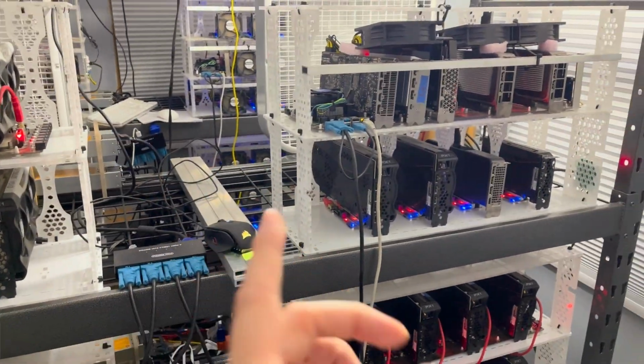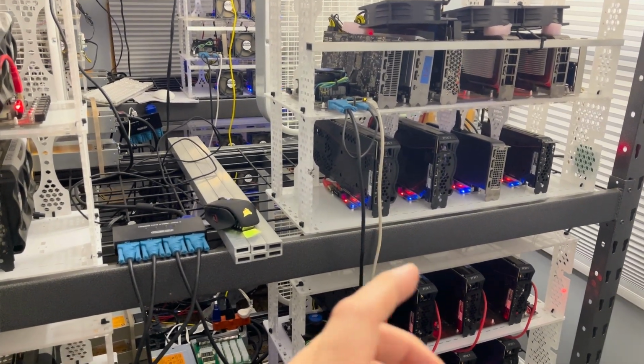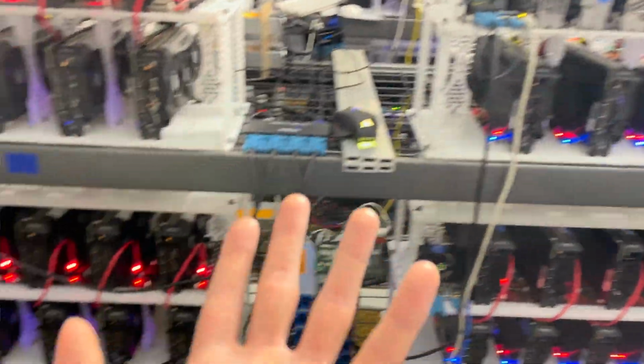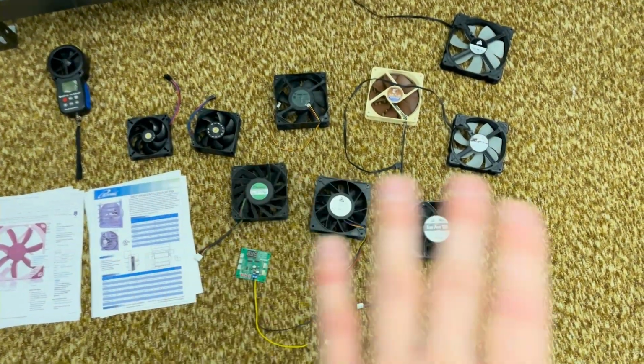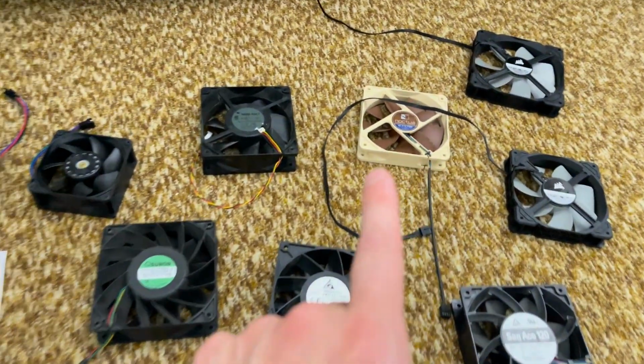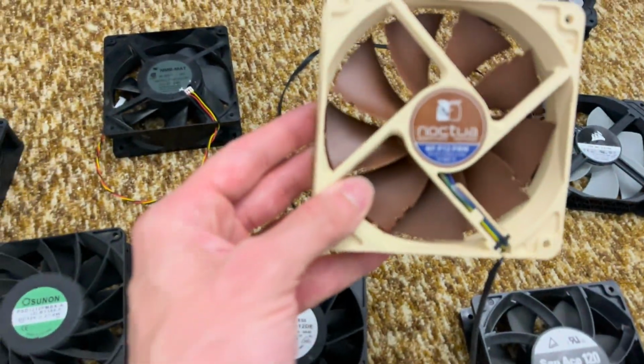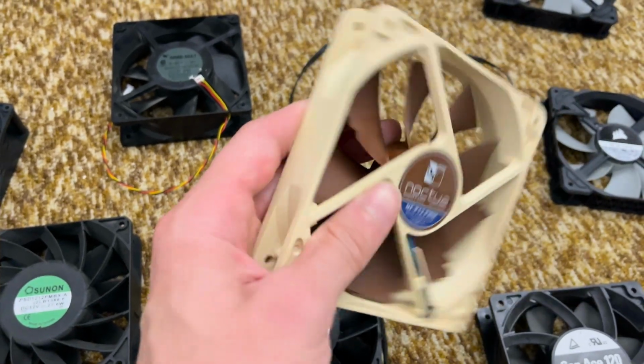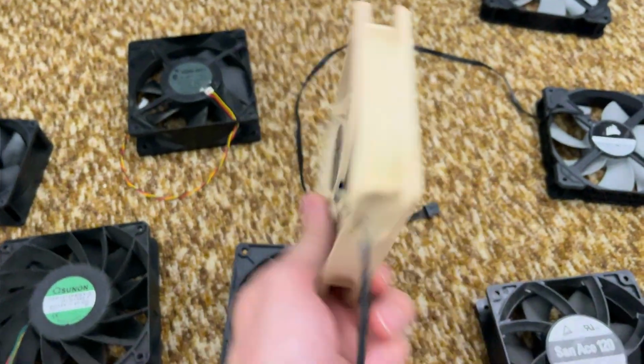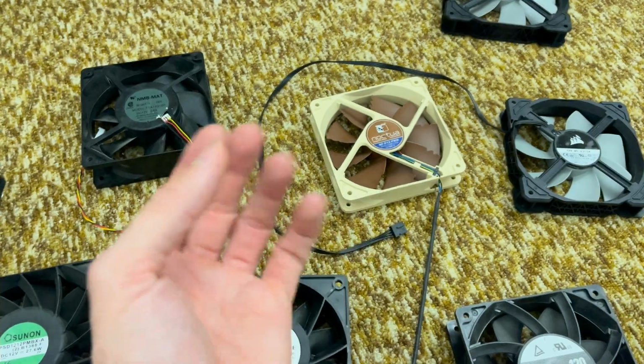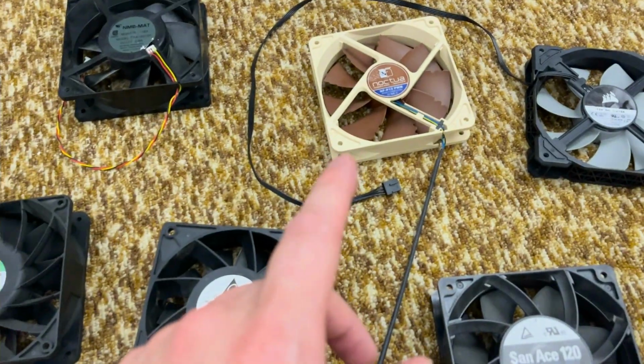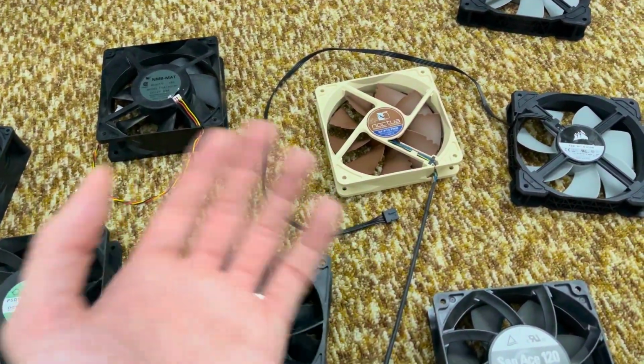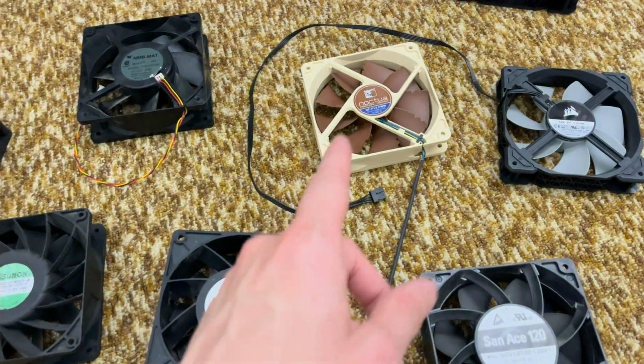So the number that the fan says, the delivered CFM, it's kind of a misleading number. You could sort of compare it from fan to fan, but not always. Some fans are designed for more pressure than others. They all have very different designs. You look at something like this. It's not to say this is a bad fan, but this is a very low power fan, 0.05 amps, made for a computer, right? Cooling a heat sink or something like that, where you have a lot of access to air. And in the event of a little less airflow, well, it doesn't really matter. And a lot of times these might not even be running at 100%.